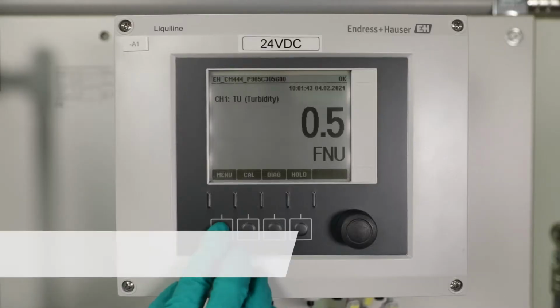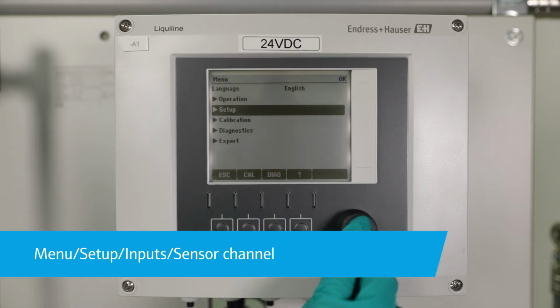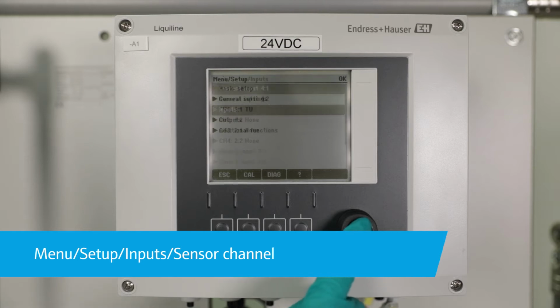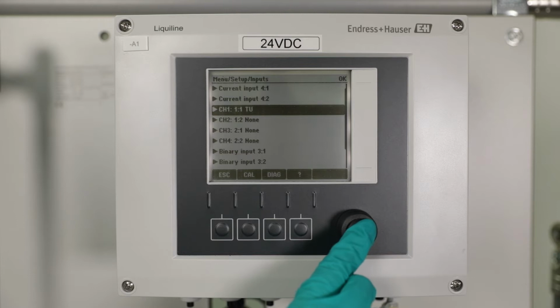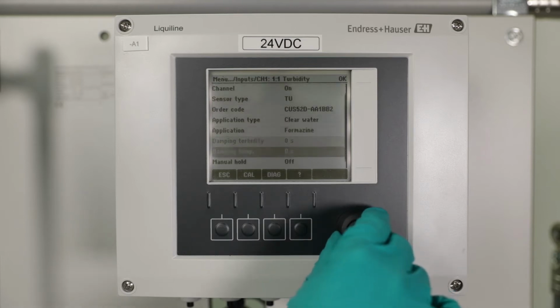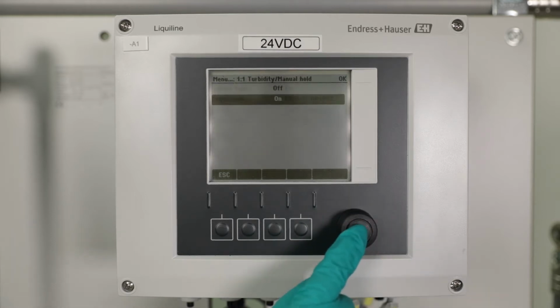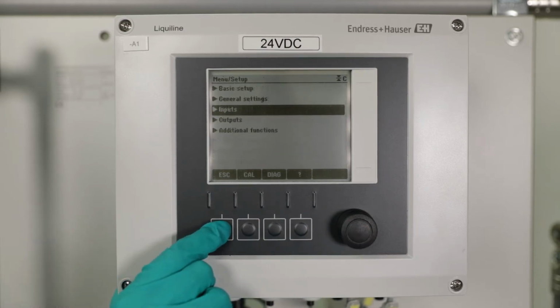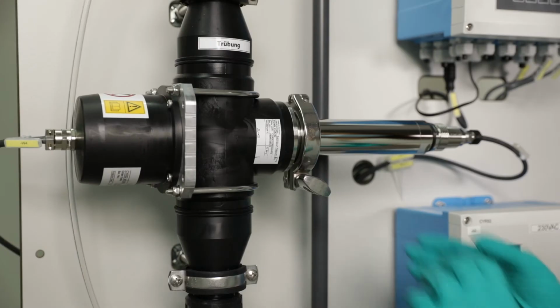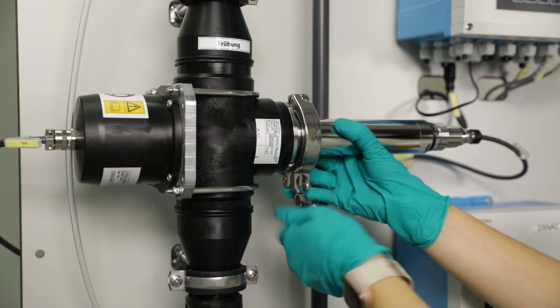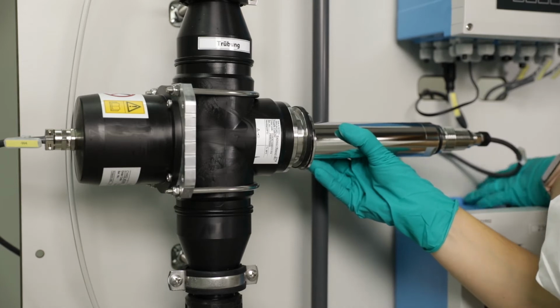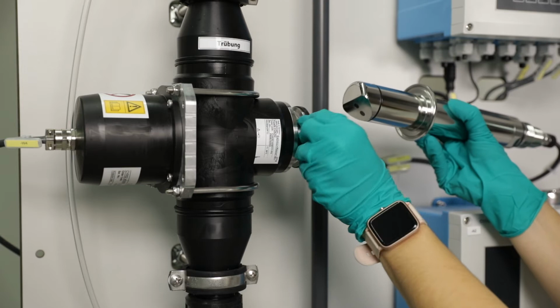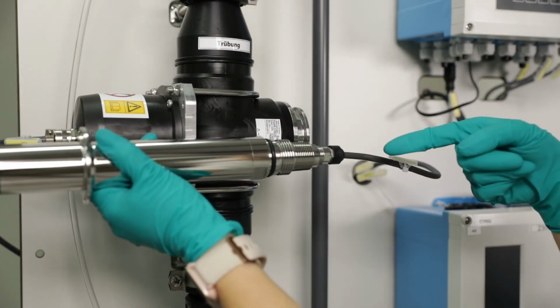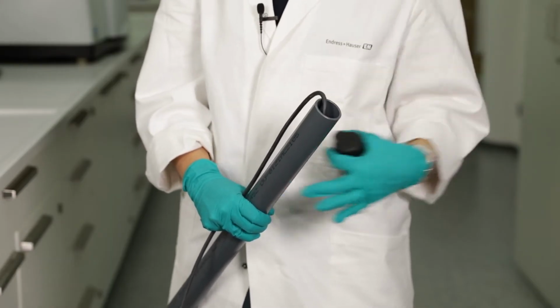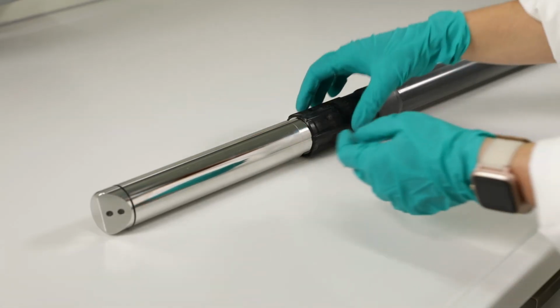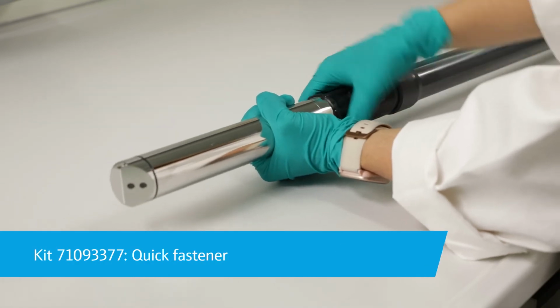For that, go to Menu, Setup, Inputs, and select your sensor channel. Scroll down to Manual Hold and set it to On. Now take the sensor out of the process. Be careful not to twist the sensor cable while doing so. If an immersion assembly is used, remove the protection cap first before you take out the sensor. Ideally, the sensor already has a quick fastener for easy removal.